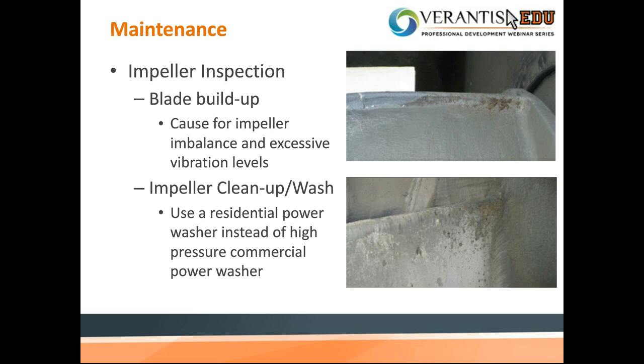Impeller cleanup and wash. We recommend you use a residential power washer. We don't want to be using a high pressure commercial washer because it just pits holes through it and ultimately gets into the base layer of the housing or of the impeller, and you could lose the corrosive protection of the impeller. And we don't want to have that. Plus, you lose some structural integrity.